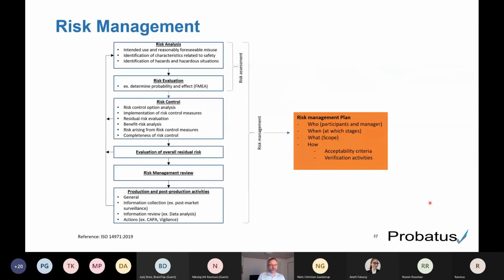So looking more into these areas with risk management, the process of risk management is to do the analysis, evaluate the analysis to identify those hazards and hazardous situations where something can go wrong during use of the device or in the design of the device, and then evaluate the probabilities and effects of these. And when we're talking about software, determining a possibility of failure for software is almost impossible.